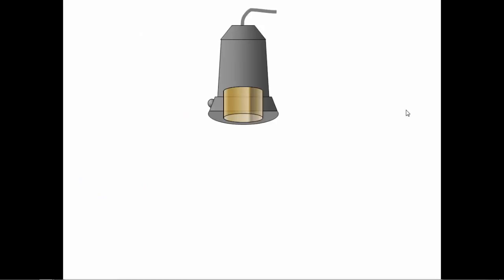So here we see with the crystal off, nothing happens. When the crystal is on and receives pulses of electricity, it pushes the molecules up against it. In our case, that's going to be the molecules in the gel, in the soft tissue and the organs of the person that we're going to be scanning, and it squishes some of the molecules together, and it allows other molecules to spread apart, and that creates a longitudinal wave, which is just like the stretched out slinky that you might remember from your physics class. So inside the transducer, there's this piezoelectric crystal, and we pulse it with electrical waves, and as we do so, it bounces in and out of the tissues.